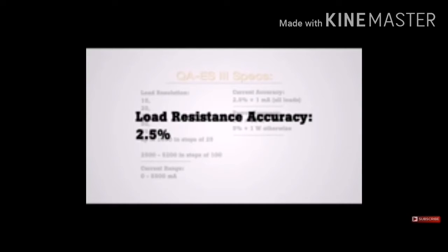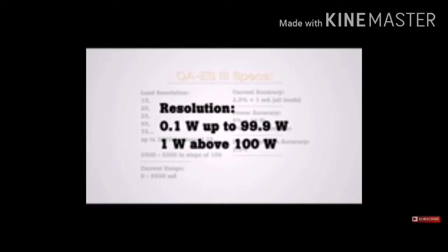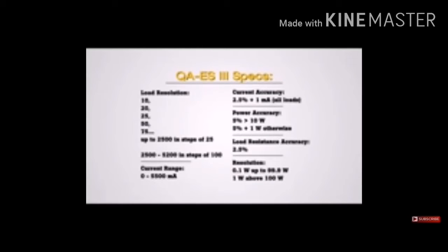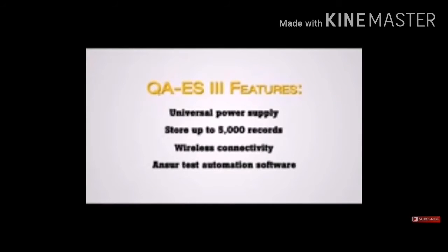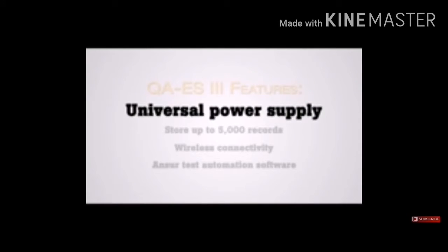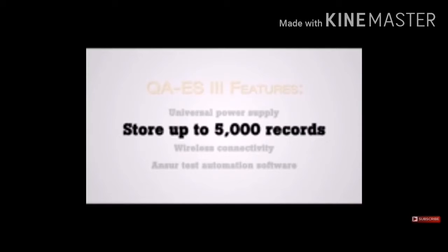In addition, it provides a load resistance accuracy of 2.5%. The QA-ES3 is also highly precise, with a 1/10 of a watt resolution up to 99.9 watts and 1 watt above 100 watts for power measurement. Featuring a universal power supply and in compliance with global standards for testing electrosurgical devices, including IEC and ANSI/AAMI, the QA-ES3 can be used worldwide. It can store up to 5,000 records, making it convenient to store results and retrieve them later.